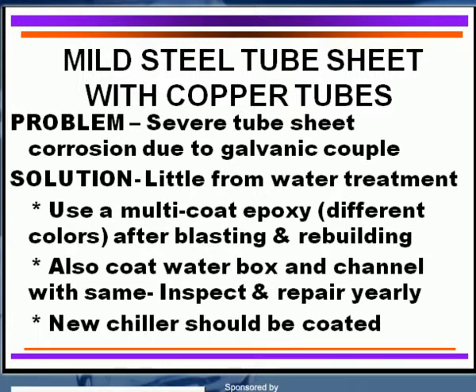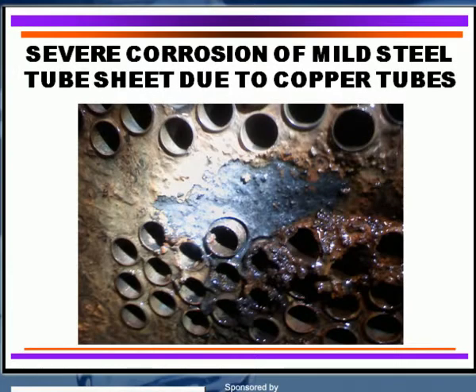And if you have a brand new chiller, the ideal thing is to get it coated with epoxy on the tube sheet prior to actually putting it in service. A number of the manufacturers can do that for you before they deliver the chiller, or you can do it once you install it, by bringing it offline and putting the epoxy coating on it.